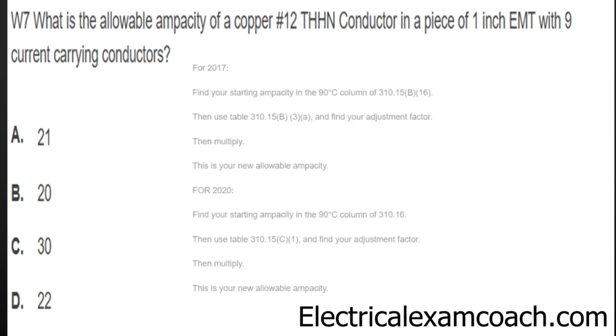Let me do the 2017 example — the same thing will apply in the 2020 and 2023, just the table names have changed. What you do is start by finding ampacity in the 90 degrees C column of 310.15 B16, our primary ampacity table.